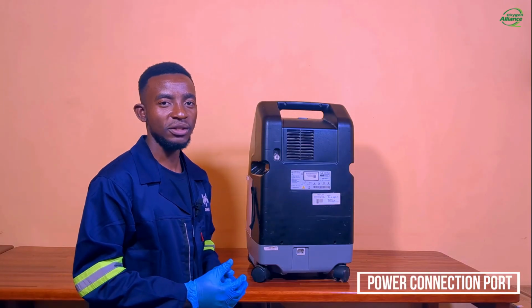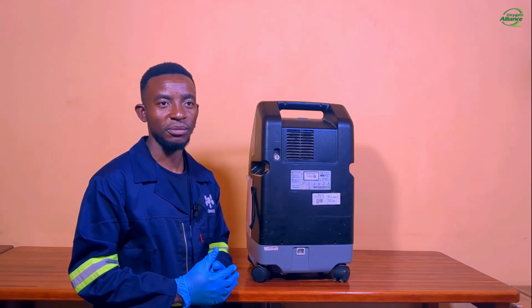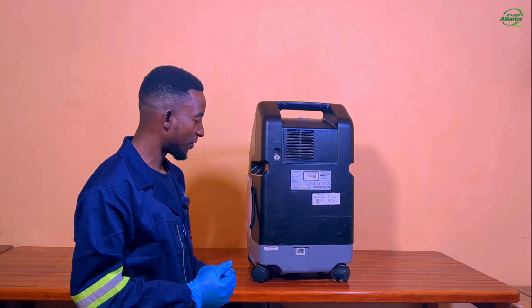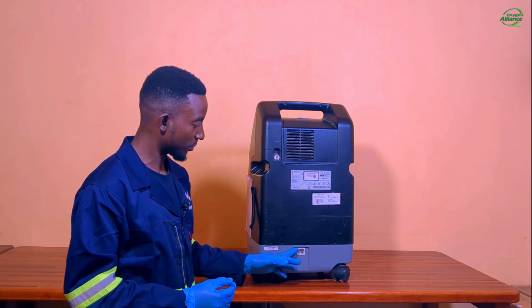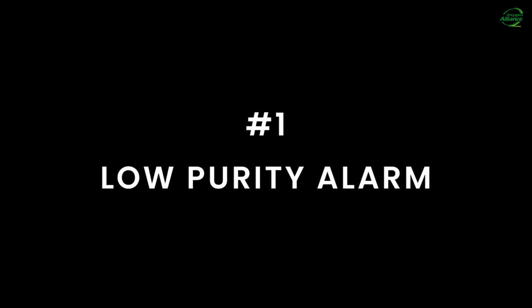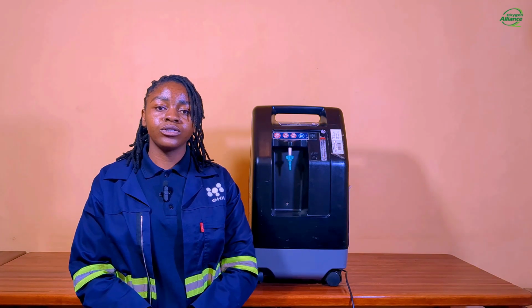So for the 1025 KS and 1025 UK model, they have an IEC power connection. This is the connector. So this alarm turns on when the purity of oxygen goes below 85%. The onboard sensor on the PCB senses the purity in oxygen, and when it goes below 85, that is when it turns on. So I will turn on the concentrator to show you the alarm.